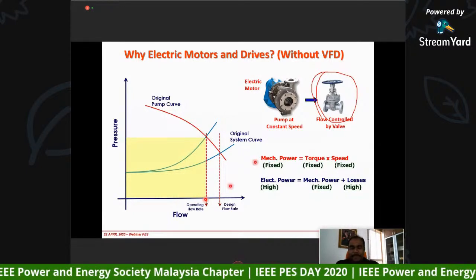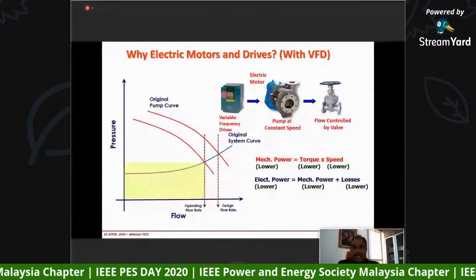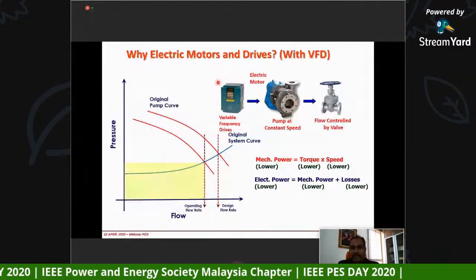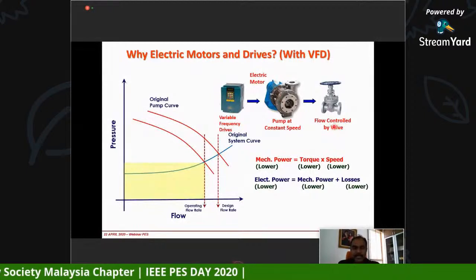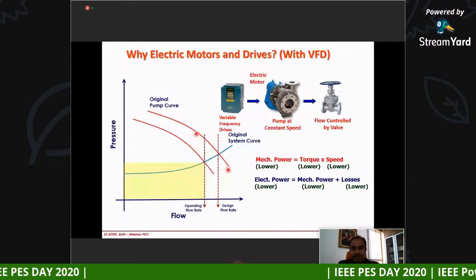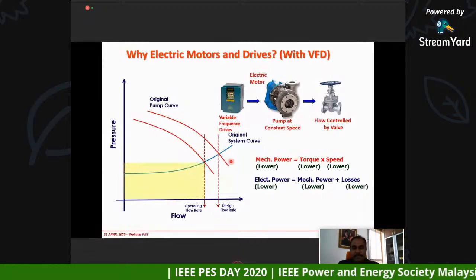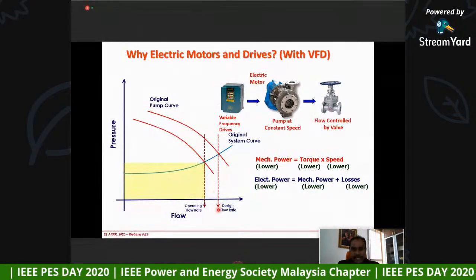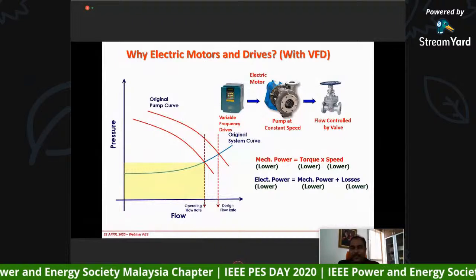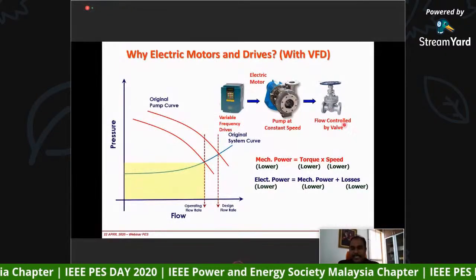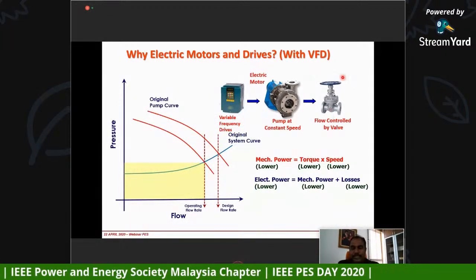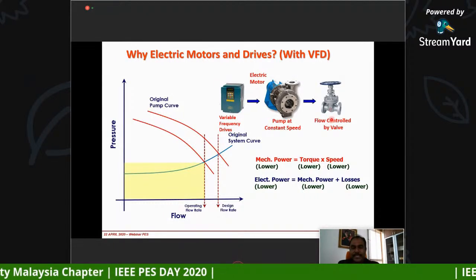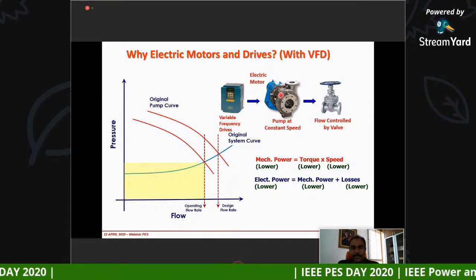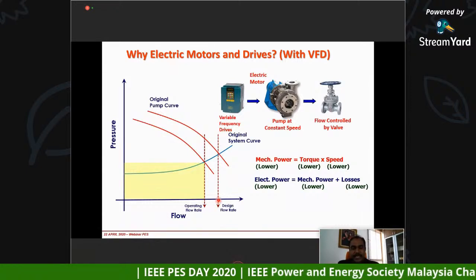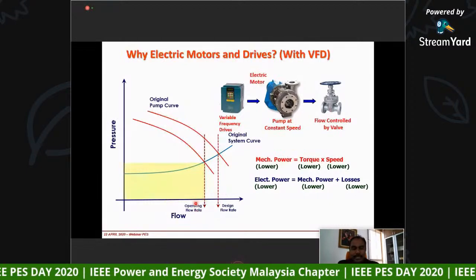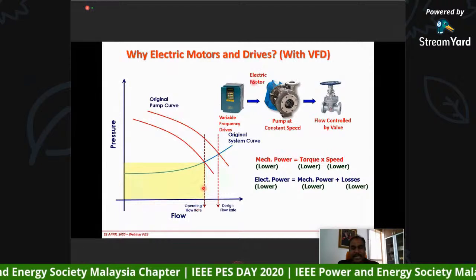Now, instead of that, let's say I connect a variable speed drive or variable frequency drive to this pump system. In this case, what I do, same thing. Originally, I select the pump system here, pump curve. Okay, I design the operating curve here with a certain flow rate here. Now, what I do is I don't control the mechanical valve. I actually fully open it. I don't control this. Okay, it's fully open. Now, what I do is I control the speed of the pump to control the flow. That means I still work at the lower, reduced flow rate, but by reducing the speed of the pump.